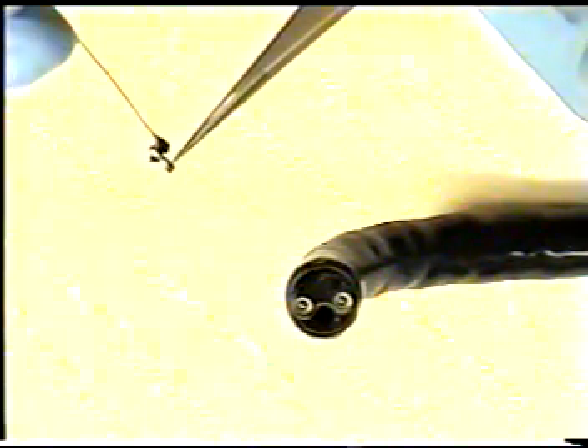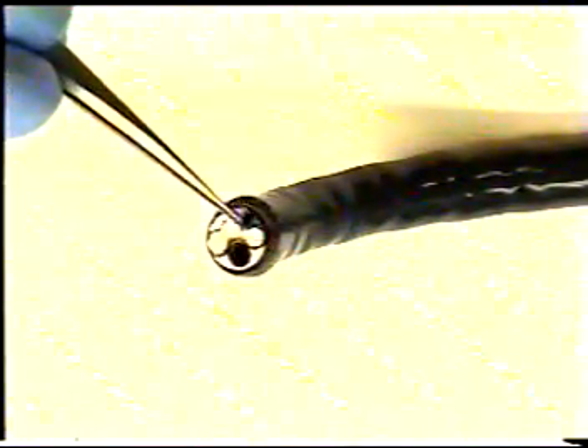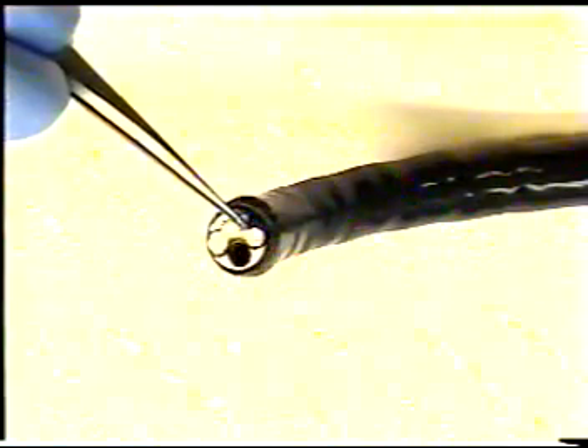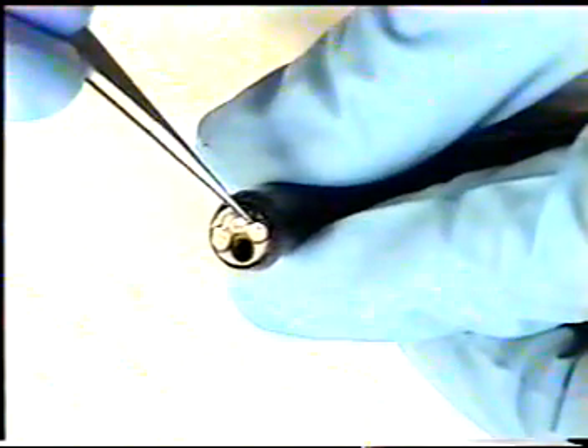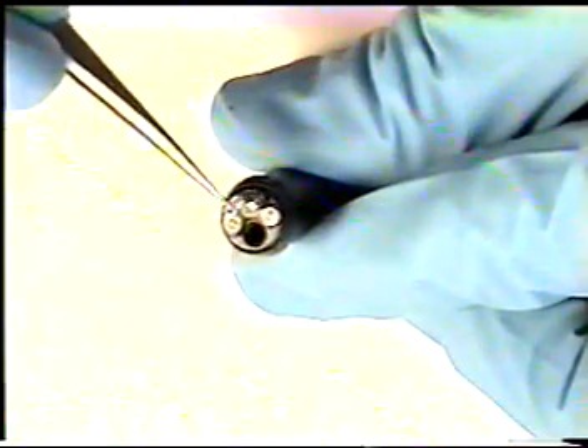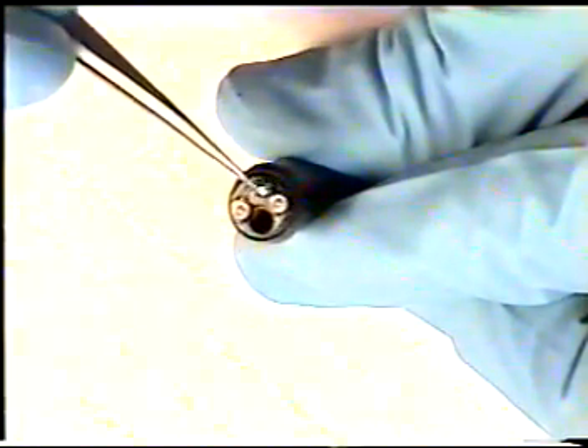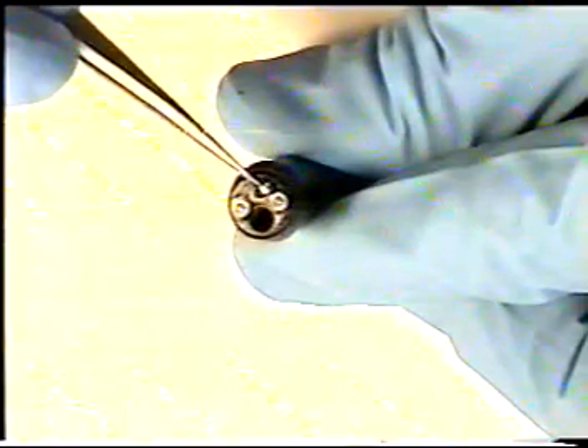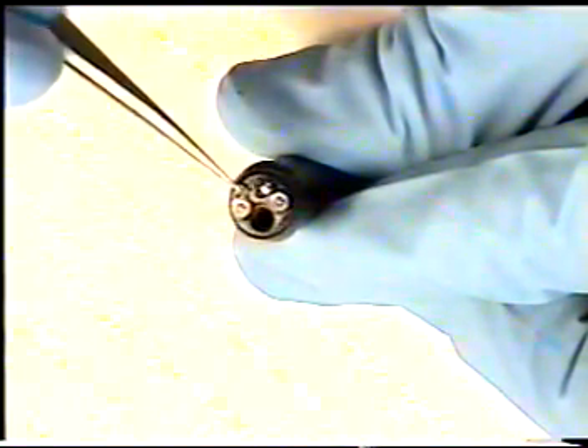Holding a new air water nozzle, apply bead of black RTV near base of air water nozzle, being careful not to let any RTV enter bottom of nozzle. Slide in the new air-water nozzle into opening, being sure that nozzle is pointing over image lens. Push lens down as to flush with image guide and distal tip.